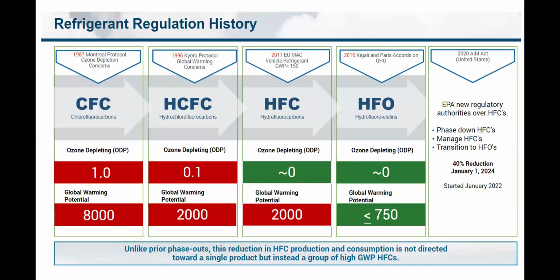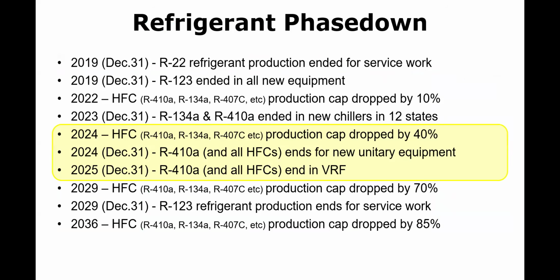So as you probably know, we have to get the global warming potential of all of our refrigerants lower. Specifically, it's got to be below 700. I know my slide says 750. That's because originally it was 750 and they changed it to 700 for who knows what reason. There are no refrigerants between 700 and 750, so it was a waste of time from your government. In any case, R410A, our most common refrigerant today, is 2088. So it's not even close. It's like 3 times too much. So we've got to pick a new refrigerant, or refrigerants, plural, that are below 700.